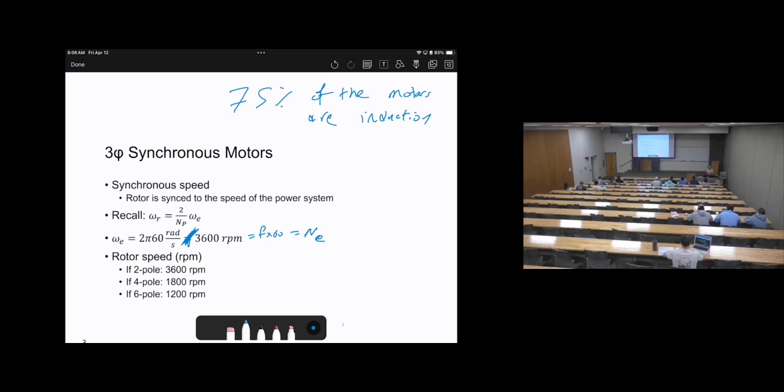In the early invention of the motors, there was no way, or it was very difficult, actually. So if you need to control the speed of the motor, then basically go to induction, because induction is easy to control. When they invented the motors and generators, the vast majority of the motors were induction, because induction allows me to control the speed, while the synchronous will work only on constant speed. So whenever you have constant speed applications like a water pump, for example, which is constantly on and off, this can be a constant speed application, then it can be fine.